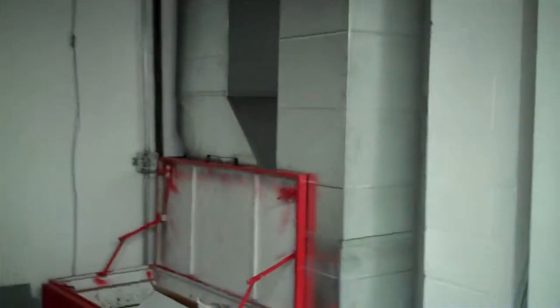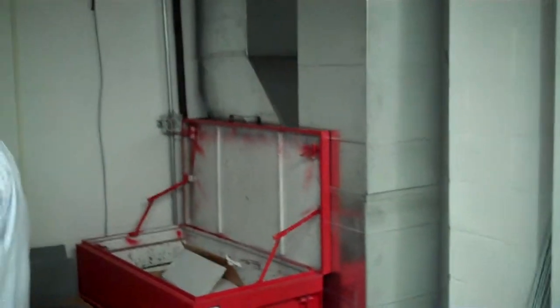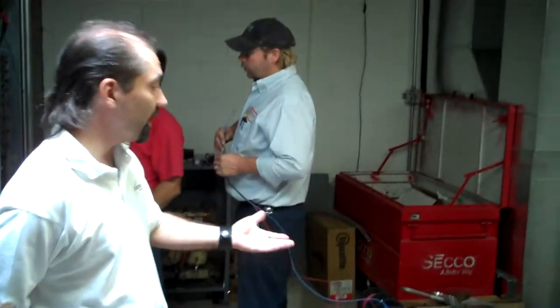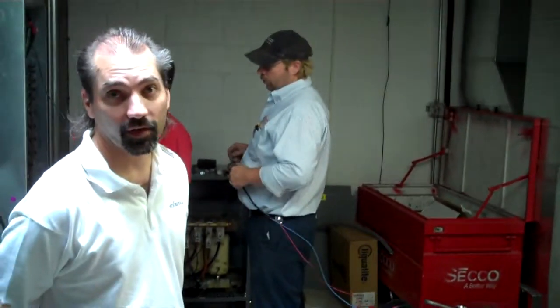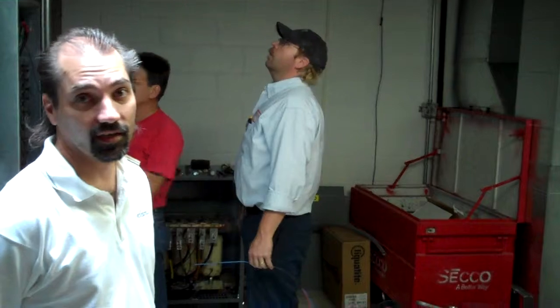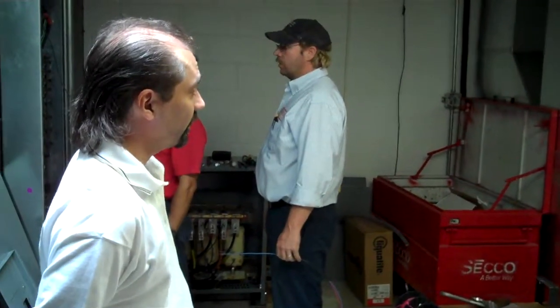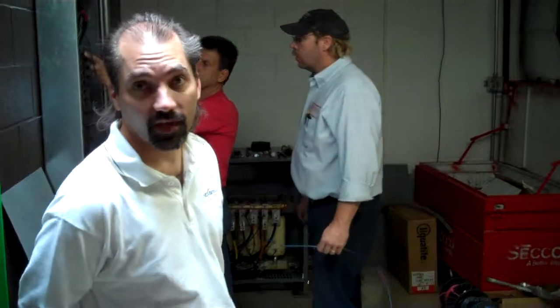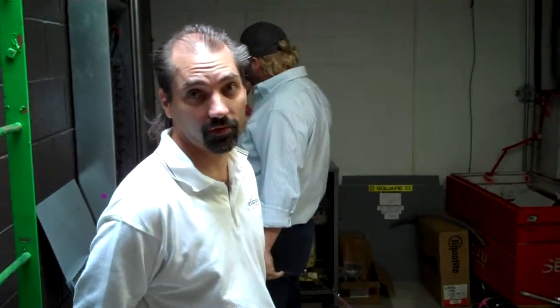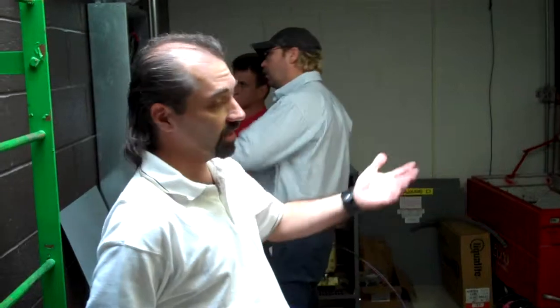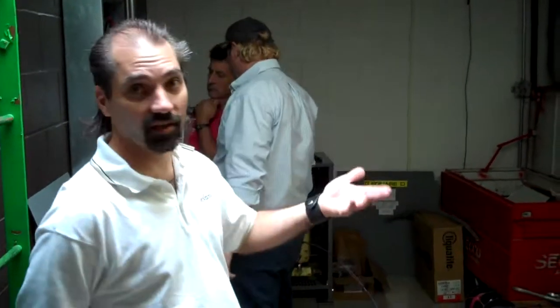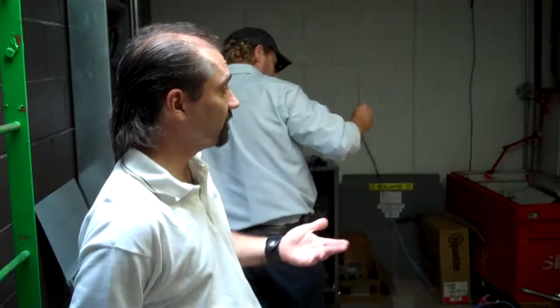Awesome. Here's the exhaust and fresh air ductwork for the first floor for the energy recovery system. Now the energy recovery system will recover up to 85% of the existing heating and cooling that's in the space. By being able to do that, we're able to save 8 tons per ERV in capacity in heating and cooling. So rather than having like 40 tons of heating and cooling on the system, we're actually able to get down to like 32 tons. Again, we're exhausting air out of the space, bringing fresh air in, mixing it with the energy that's recovered from the space, and keeping a good indoor air quality environment for the students and the teachers.